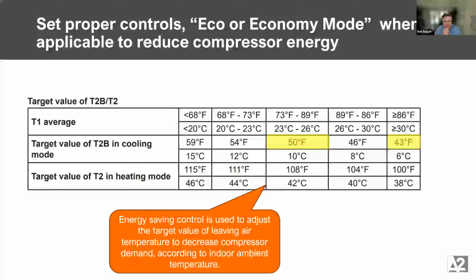And we could probably get lost in the weeds on these little tables, but this is just showing some examples of how it uses this table. If this setting is configured, it will look at the room temperature and change its cooling numbers and change its heating numbers. And again, kind of moving how that compressor works to be more efficient.